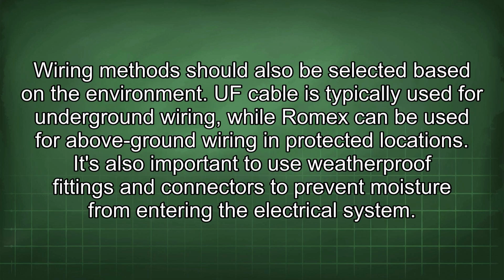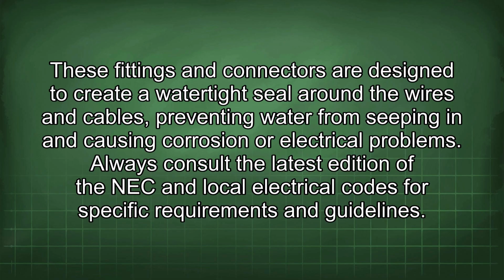Wiring methods should also be selected based on the environment. UF cable is typically used for underground wiring, while Romex can be used for above-ground wiring in protected locations. It's also important to use weatherproof fittings and connectors to prevent moisture from entering the electrical system. These fittings and connectors are designed to create a watertight seal around the wires and cables, preventing water from seeping in and causing corrosion or electrical problems.